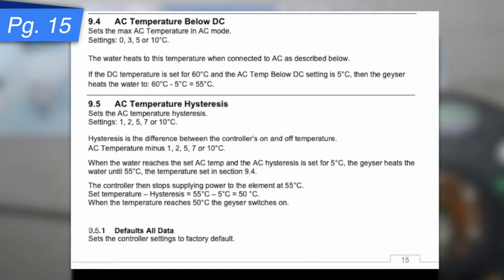But currently it is set up default 10 degrees, and there's the AC temperature hysteresis information as well. That is what the default settings are on page 15. So if you want to change those, you would need to do the dip switches, which we'll go through just now, or use the Wi-Fi module.